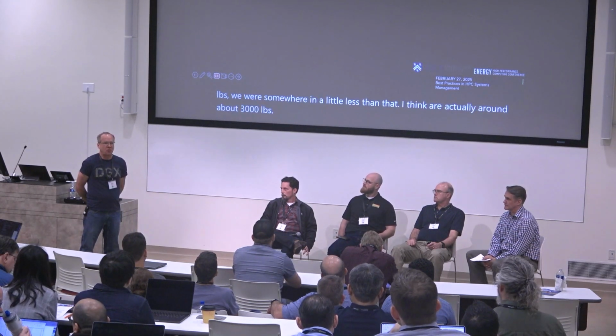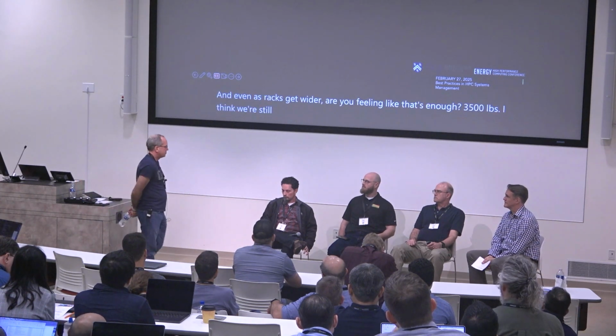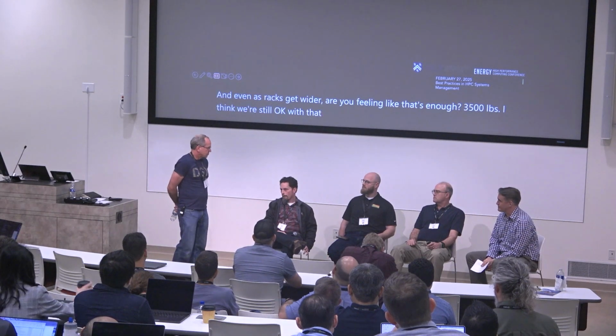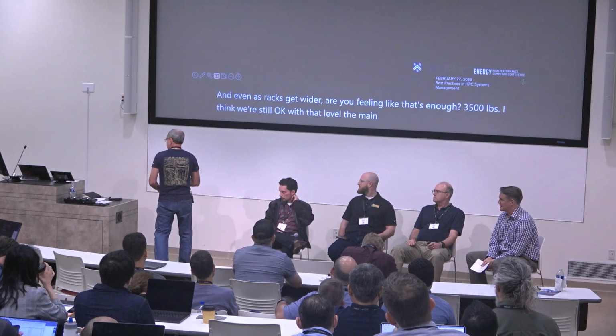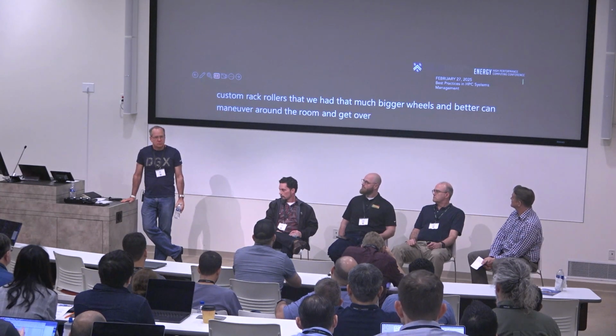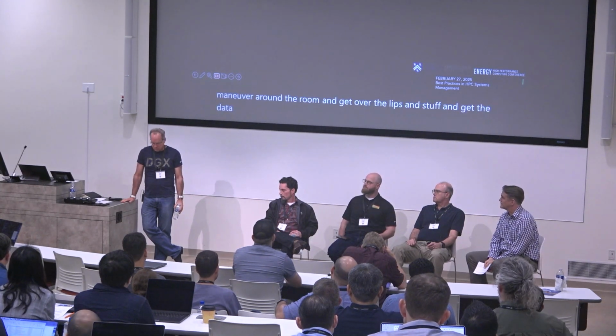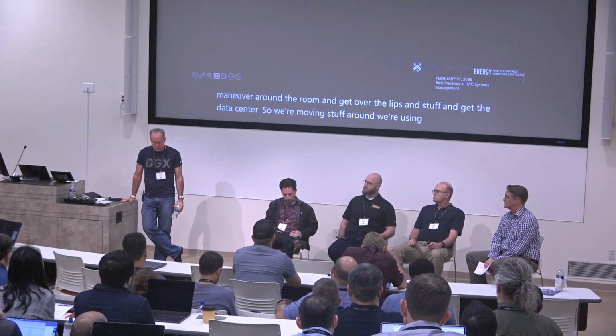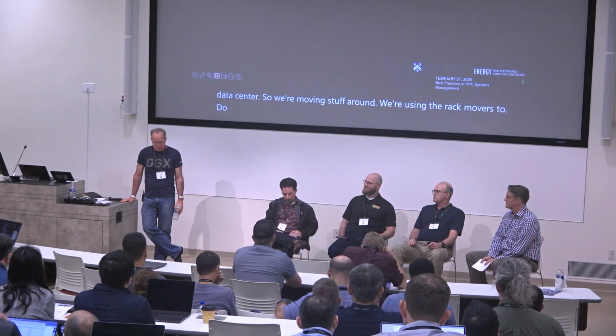And even as racks get wider, are you feeling like that's enough, 3,500 pounds? I think we're still okay at that level. The main concern I really have is rolling the racks around, and we do use our own custom rack rollers with much bigger wheels that can maneuver around the room and get over the lips in the data center. So when we're moving stuff around, we're using the rack movers, and that helps spread the load across more of the tiles.